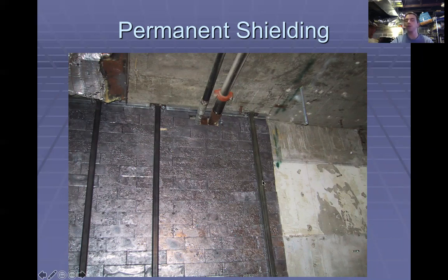That's something you have to plan strategically so you don't have gaps where the radiation is just flying through. You can do that a number of ways. You can do angles through the wall so it's not a clear straight shot through. You can put them in locations that are not going to be occupied by people. There's a lot of strategies for that. And generally, when we take dose rates around these areas, we don't see any truly elevated rates that we would be concerned about, though that's not always the case.